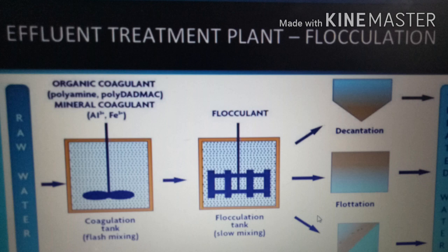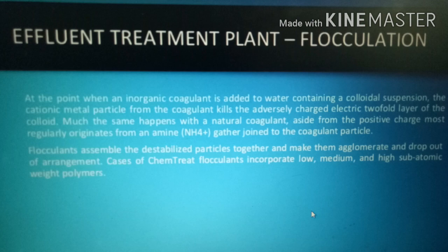When an inorganic coagulant is added to water containing a colloidal suspension, the cationic metal particles from the coagulant neutralize the negatively charged electrical double layer of the colloid. Much the same happens with an organic coagulant, except the positive charge most commonly originates from amine groups, NH4+, attached to the coagulant molecules.